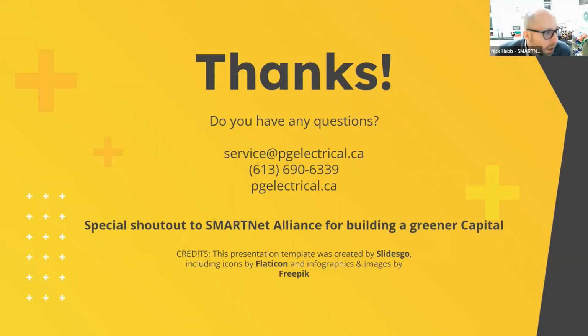Tim's wondering, in a residential property, if solar or battery systems are being considered after renovation and panel upgrade, would it be wise to install a master 200 amp disconnect between the incoming mains and the panel? Yeah, there's combination load centers, and then there's load centers with a separate disconnect. A lot of times it makes sense to have things split out a little bit. So if you're planning to add a bunch of equipment, especially if you want something like an automatic transfer switch, it's a great idea to put in a few extra disconnects just so you can isolate components.